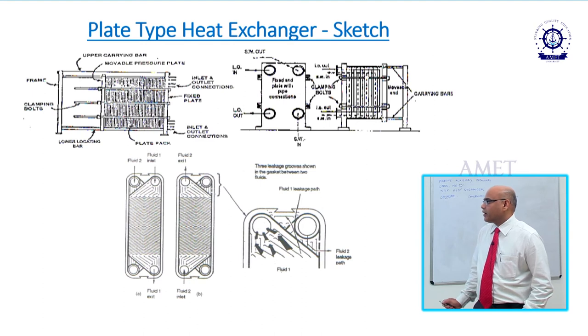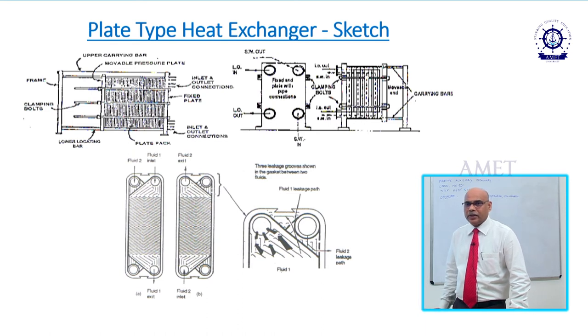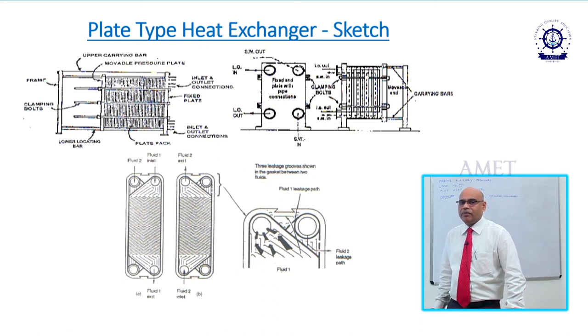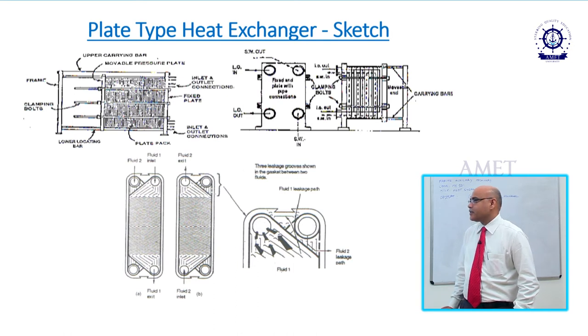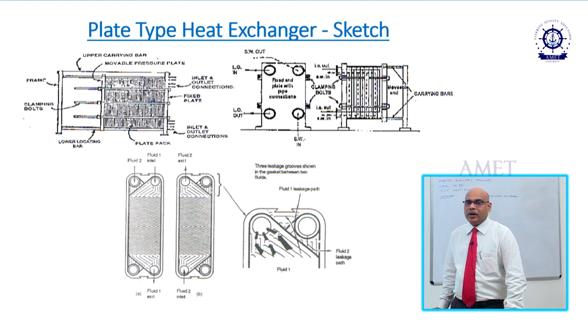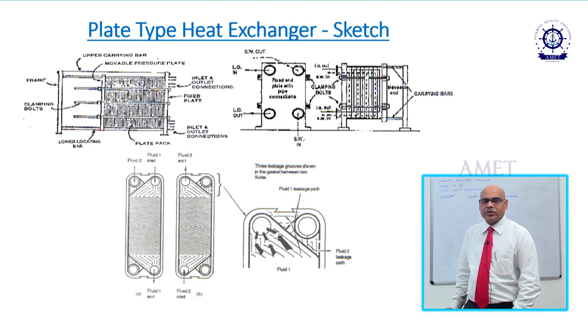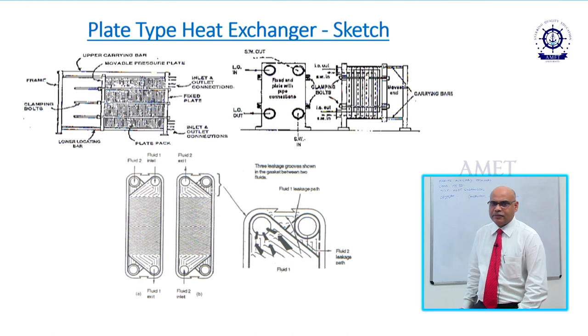Before dismantling, read the manual carefully and measure the distance between the plates at the top, middle, and bottom on both sides. Record these measurements because we must ensure the plates are not over-tightened or left slack at the end of maintenance work. After removing the plates, move them to the other end, clean them with a wire brush, check for deposits, clean the deposits, and make sure the gaskets are not damaged as they are made of nitrile rubber and are very expensive.